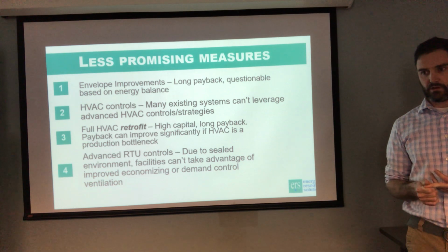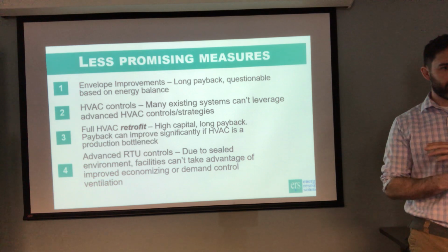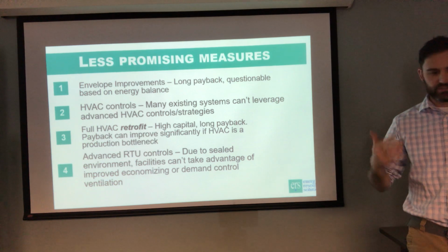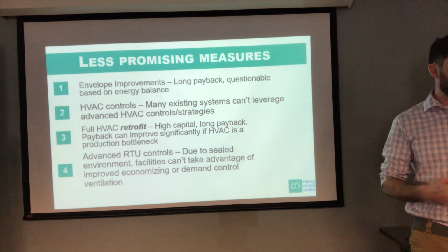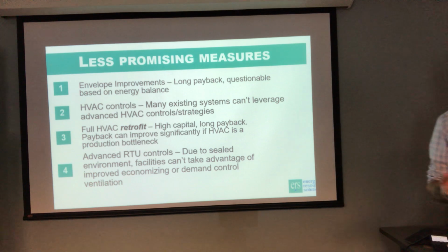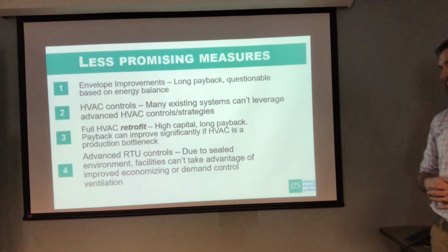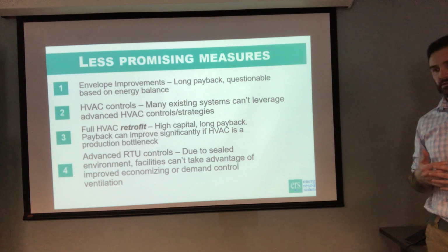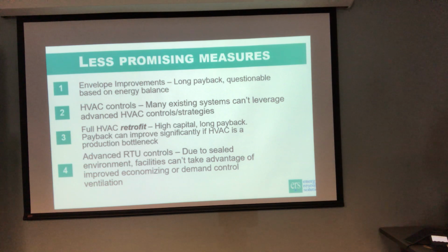These facilities are exothermic, meaning they're always rejecting heat—the internal loads are so substantial. So if we improve the envelope, we're just doing a better job of trapping that heat within the space, meaning we now rely 100% on the mechanical equipment to remove it. If the envelope isn't quite as good, there's more opportunity for that internal heat to migrate through and be lost.